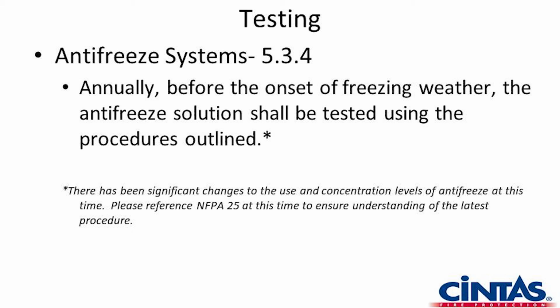Well, years ago, when we were filling an antifreeze system, we would take a hydrostatic test pump, a pump that we use when we are commissioning a system, and we would pump antifreeze and try to match that with the rate of water that we were filling the system with. The problem is you either get too much water or you get too much glycol. It wouldn't mix properly, so you would have an antifreeze system that would either be 100% glycol or 100% water, and you would still have a pipe that would burst during the winter months.